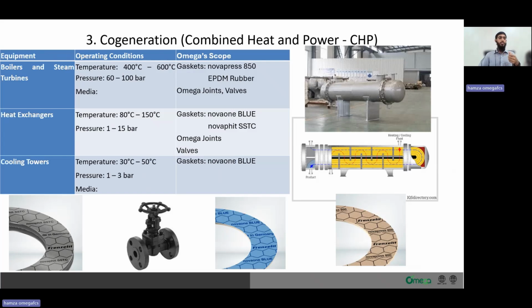So the equipment that we see here are boilers and steam turbines, which see a temperature of 400 to 600 degrees. Pressures are 60 to 100 bars, and the media here again remains water. The gasket that can be utilized here is novapress 850, or in case of metallic gaskets, they are also seen in the system. For lower temperatures, we can use EPDM and rubber gaskets to seal the fluids inside. Omega joints again play a very important role in this boiler and steam turbine system, where pressure spikes are very detrimental to the piping system, and we also utilize valves to control the media, to control the inlet of the steam to the turbines.